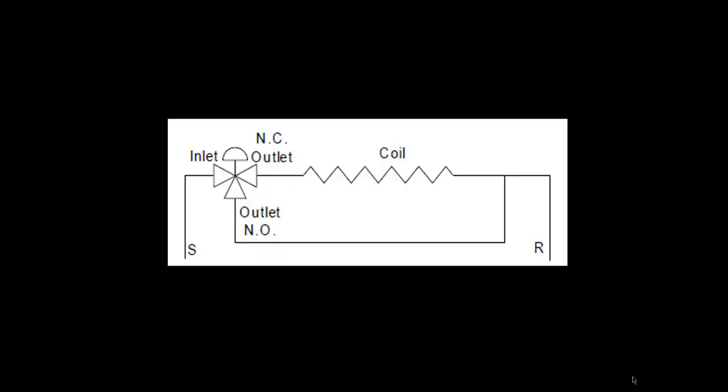Diverting valves in bypass applications are placed upstream of the coil. The supply water enters the inlet port and is directed to either the coil branch or the bypass branch, depending on the signal from the controller to the valve actuator.